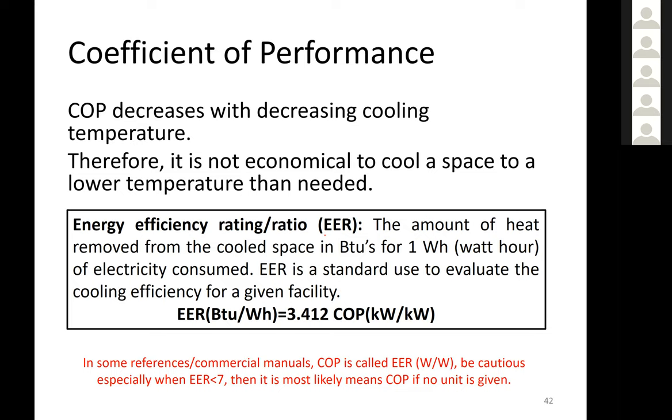One very important thing that will lead us to talking about dual heat pumps is that COP decreases with decreasing cooling temperature. So it's not economical to cool a space to a lower temperature than needed, because at that point COP is going to drop. COP is always inversely proportional to the difference between the high temperature and the low temperature. When I say the high temperature, I'm talking about the condenser side, and low temperature, I'm talking about the evaporator side. When this range is small, then COP is going to increase.